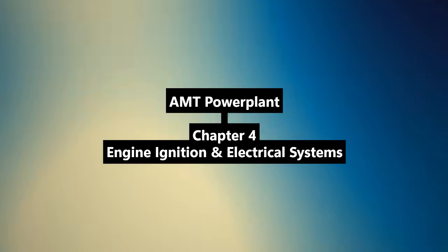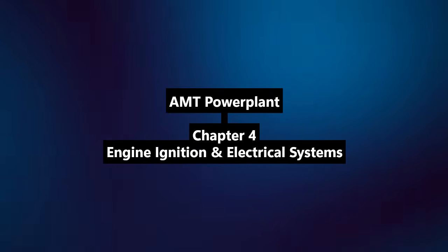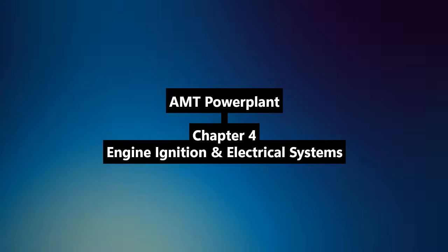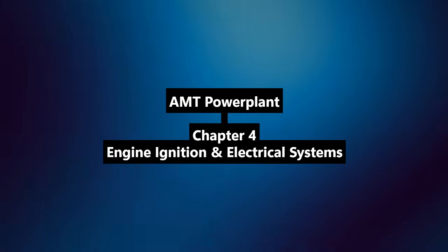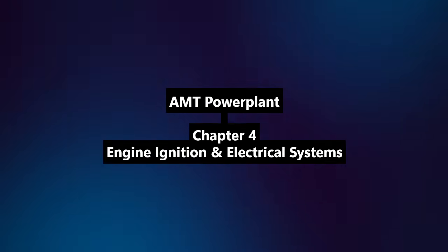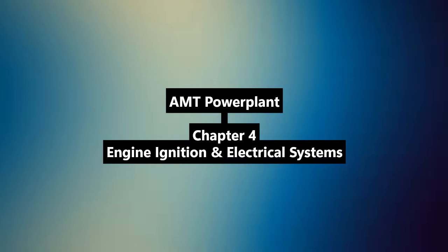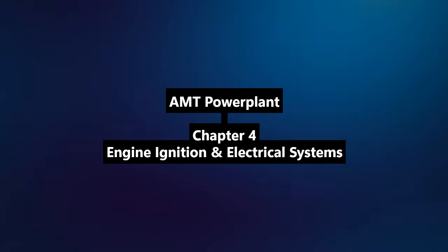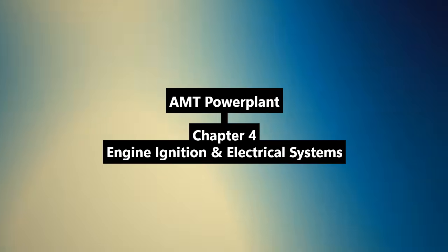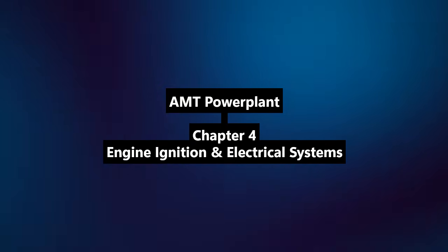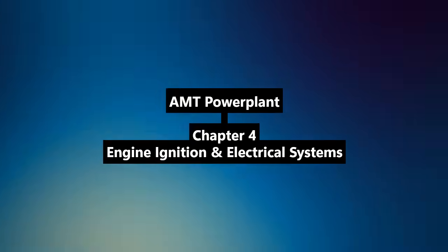Oh, absolutely critical. And the chapter also points out, importantly, that the air circulating through the ignition system needs to be clean and, crucially, oil-free. Oil's bad too. Yeah, even a thin film of oil on ignition components can significantly increase the likelihood of flashover and subsequent carbon tracking. Got it. Keep it clean, keep it dry, keep it vented.